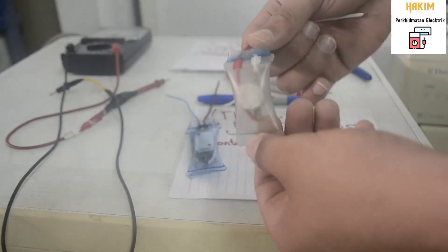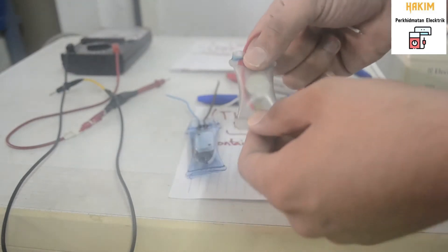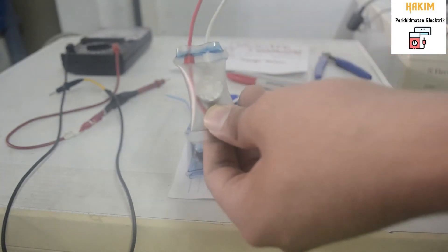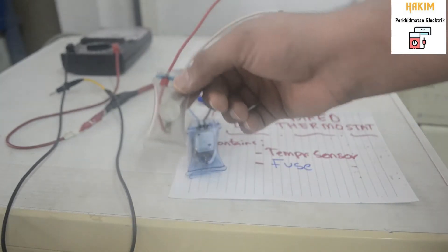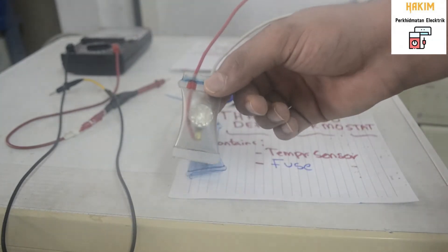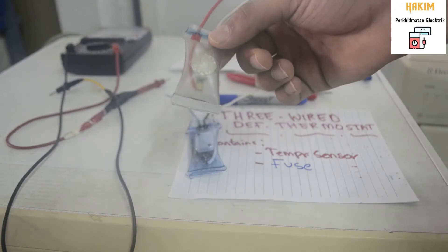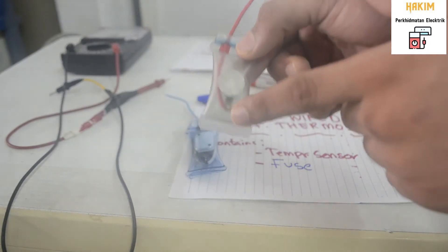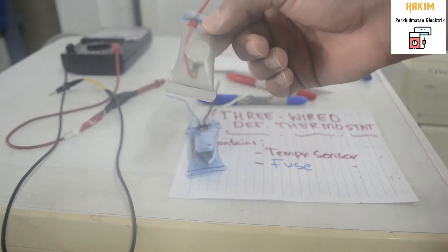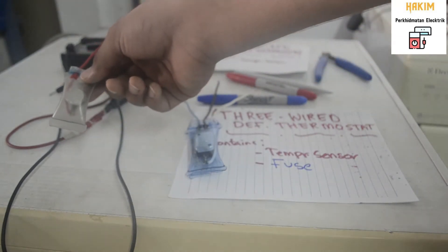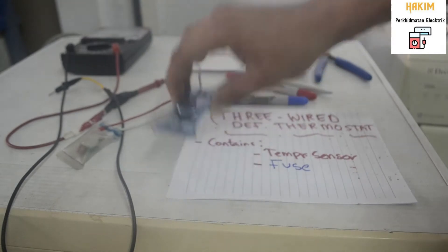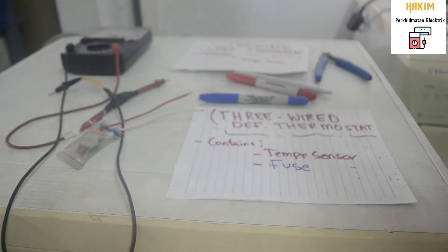We had a case last time. On this, sadly, there is no fuse here. So if the heater is turned on for a long time and this is broken down, the heater is also going to be broken down, stopped working. But maybe in some fridges, there are another separated fuse to the heater. So that is also sort of safety.